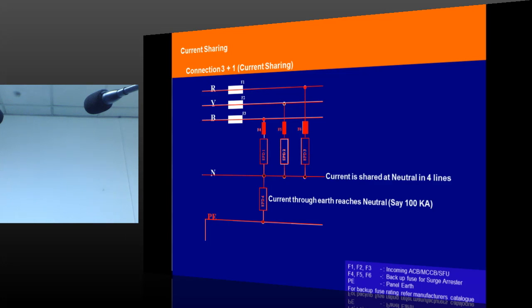Under the first condition, equipotentialization, you imagine that in one of the previous slides I explained that 50% current goes to ground and 50% can come inside the building. And the amount of current which is coming inside the building needs to be taken out. So this SPD should be installed in such a way that the SPD is able to divert the lightning current towards the service. Instead of coming inside the building, it is diverted towards the service. So in one of the first slides I told, lightning current is maybe class level 100 kA, class 1 200 kA. In case of 200 kA, 100 kA goes to earth, and 100 kA will come inside the building, and that 100 kA will flow through these SPDs. 25 kA will flow through each SPD, and this is how the SPD current ratings are derived.